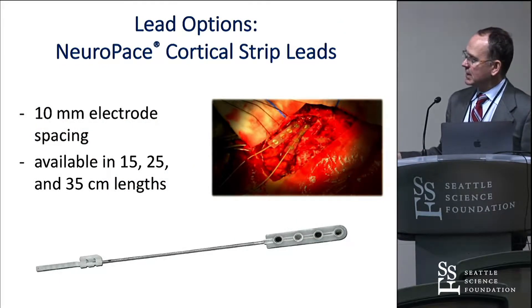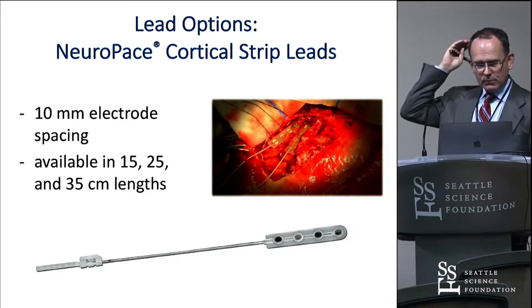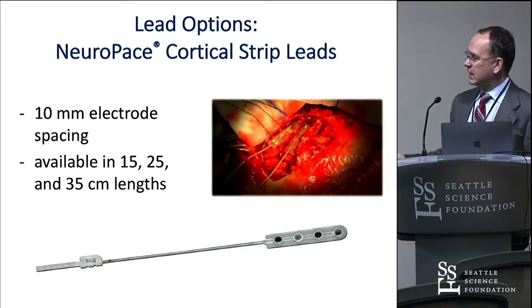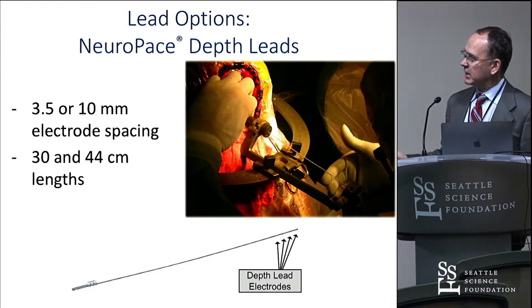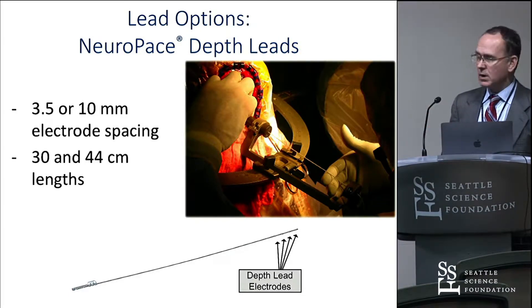For strips, there are different lengths available — 15, 25, and 35 centimeters — all with 10 millimeter spacing between each contact. It's important to plan where your electrodes will be in relation to the device to know what size lead you'll want for any given case. For depth electrodes, there are two different intercontact spacings: 10 millimeter spacing, commonly used in mesial temporal lobe, and 3.5 millimeter spacing, which might be used in cortical dysplasia or a more compact target.